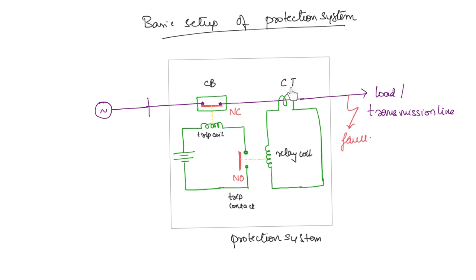Now, this CT that is present here is called the current transformer. Under normal working operation, it is not going to react, but when a huge amount of current flows, then by transformer action, a current is produced in the secondary of the CT, and a current will flow in this circuit. Here we have the relay coil. Once the relay coil is energized, it will attract this contact. This is normally open, so under normal operating conditions it will be open. When the relay coil is energized during the fault, this contact is attracted towards the coil and it will now close.